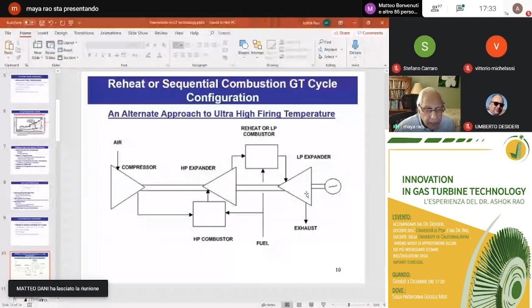So you have the high pressure expander, which does partial expansion. And then the exhaust from here goes to the reheat combustor, where you burn additional fuel and then complete the expansion cycle. And this shows the temperature entropy or the enthalpy entropy diagrams for the conventional combustion, that is single combustor, simple cycle gas turbine on the left. And then on the right is that for the reheat cycle. You have compression, heat addition by combustion, partial expansion, again heat addition, and completing the expansion cycle. And the same amount of work, the same amount of specific power, can be produced by not going to such high firing temperatures as you would require with the conventional combustion.